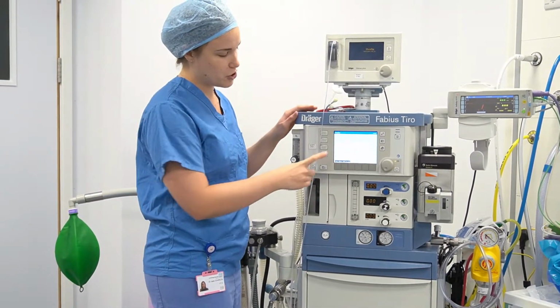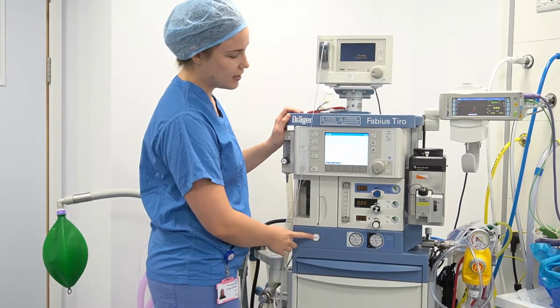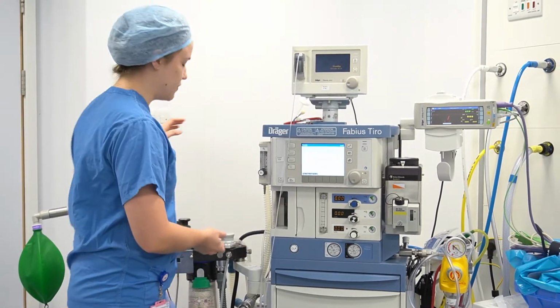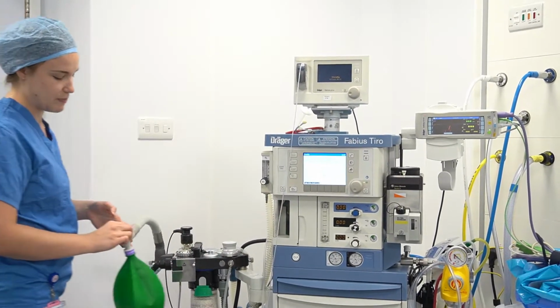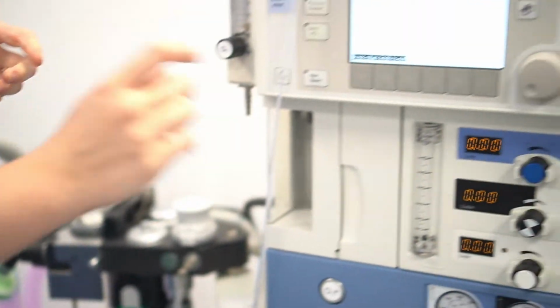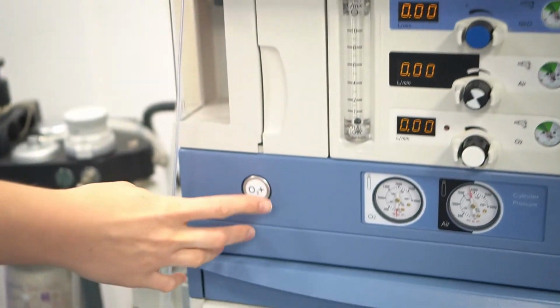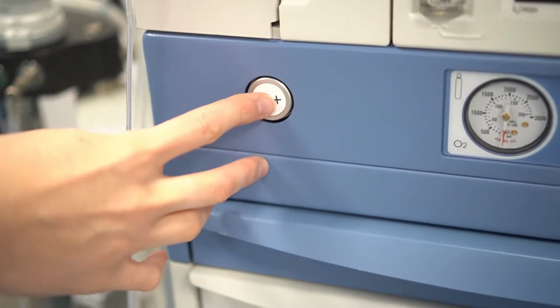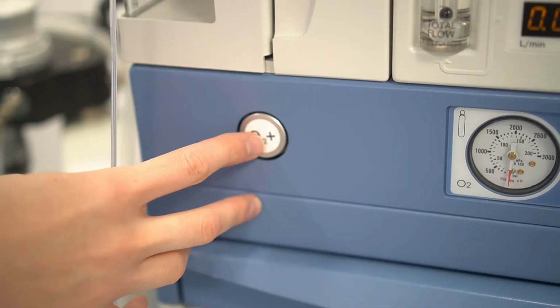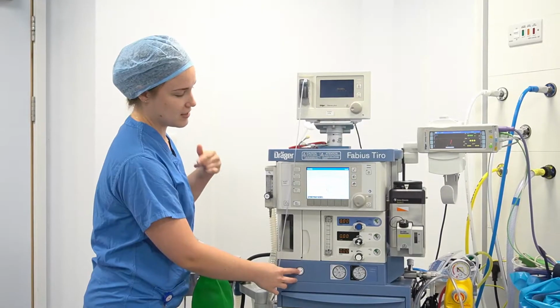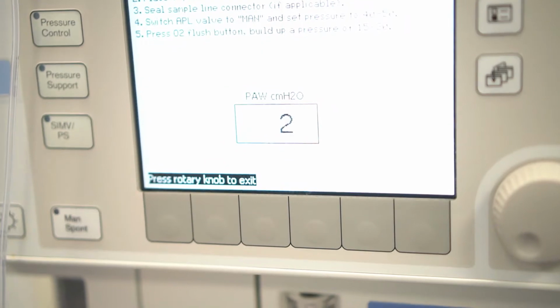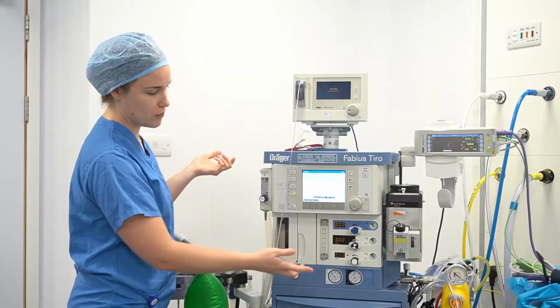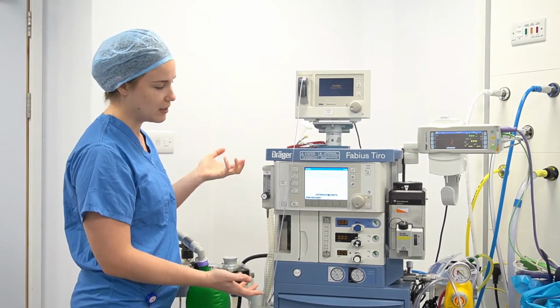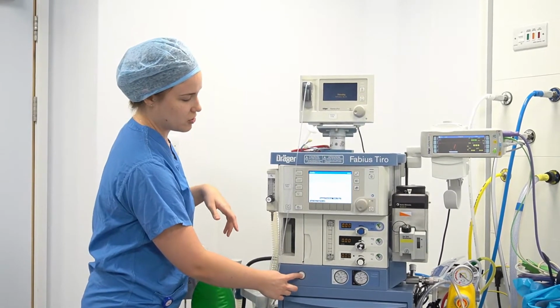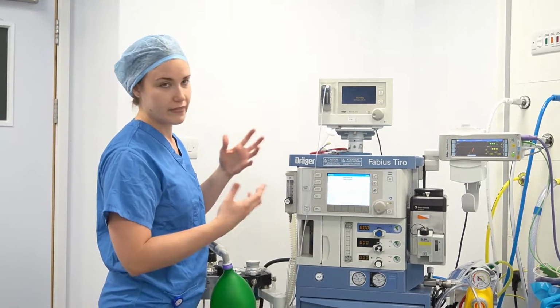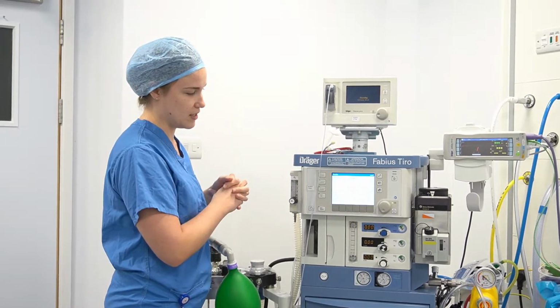And the last is to push the O2 flush, which you can find over here, to build up a pressure of 15 to 30. This pressure build-up takes place in your bag, and you'll see the number read over there, so it happens quite quickly. I'll just show you, too much pressure will look like that, and then it will say pressure overshoot and to retry that step. So again, you just do the same thing, but let go a bit quicker. And then it will actually have a chance to run that test.